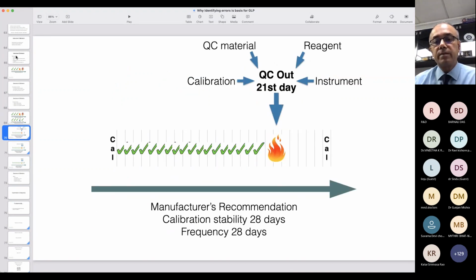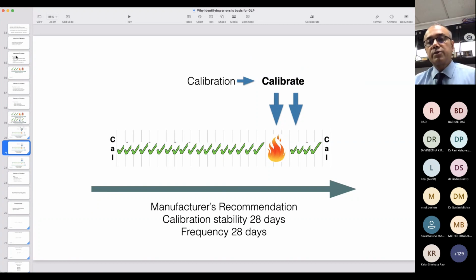And this is what I mean. The manufacturer's recommendation for calibration stability is say 28 days. So we put 28 days as the calibration frequency, but on the 21st day, we have a QC going out. Now the QC going out could be due to various reasons, and it could be instrument, reagent, QC material, and calibration. If the QC has gone out because of calibration, then what I'm going to tell you now is going to apply. Okay, so the QC has gone out on the 21st day of the calibration frequency, which is actually 28 days. Now what do we do? We typically calibrate after the QC has gone out, and we continue the 28-day calibration schedule.